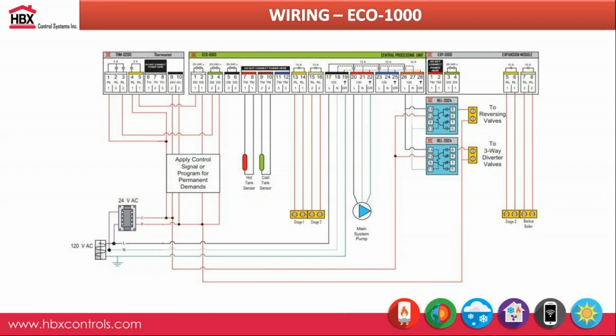One of the bigger things that we get tech calls on in terms of the geothermal controllers is that people think that once the tank temperature drops below or above a certain set point, it will automatically send a heating or cooling demand, depending on how it's set up. We always need a heating and cooling demand. We need some auxiliary controller out there, like a thermostat, to give the controller permission to actually turn on for heating or cooling.